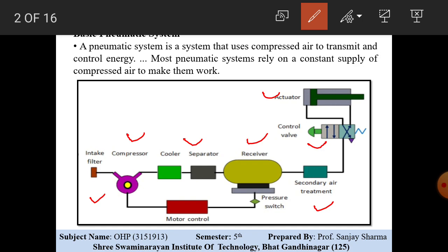The air entering the compressor is compressed and supplied to the receiver. A cooler and separator are provided so that the air temperature drops, volume reduces, and whatever vapor particles are present in the air will be condensed and separated in the separator. That air then enters the receiver, and from the receiver it goes to the secondary treatment. At many places where very low pressure is required, only a separator or secondary air treatment plant is provided.